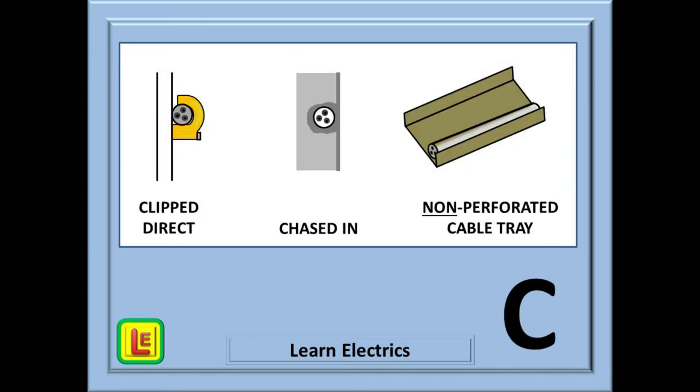What can we make of this slide? A cable can be clipped direct to a wall with a cable clip or similar. A cable can be chased into the wall and skimmed over with plaster. A cable can be on a non-perforated or complete cable tray. Hopefully, you're ahead of me now. What letter does clipped direct begin with? C. What letter does chased in begin with? C. And what letter does complete cable tray begin with? C. What is the reference method then? C.